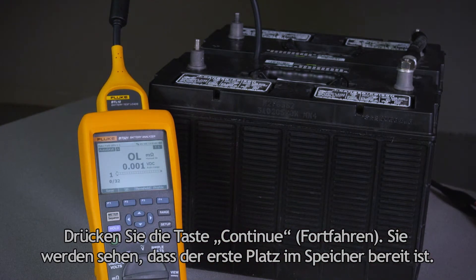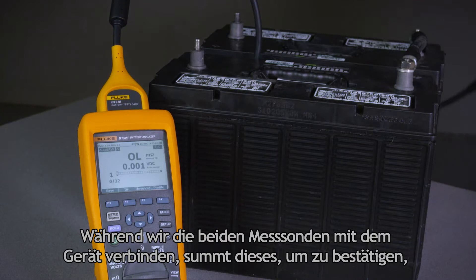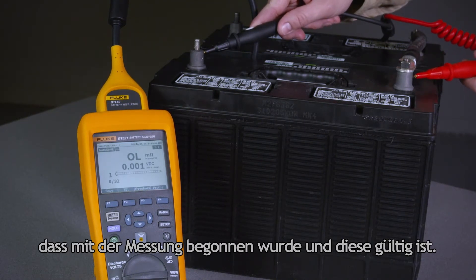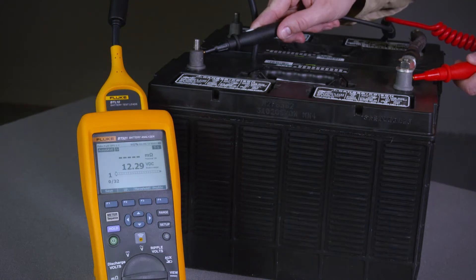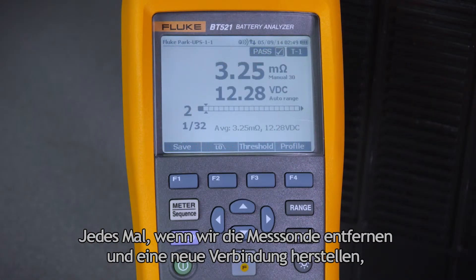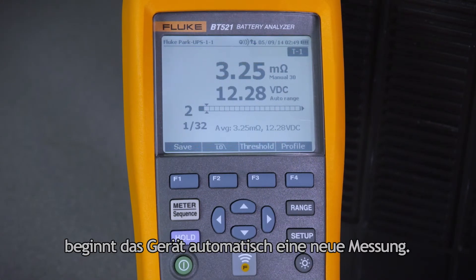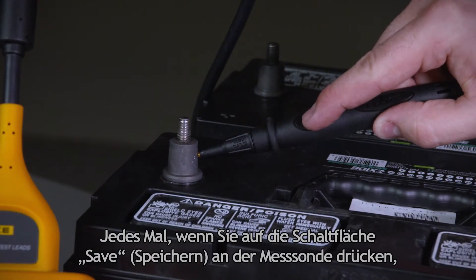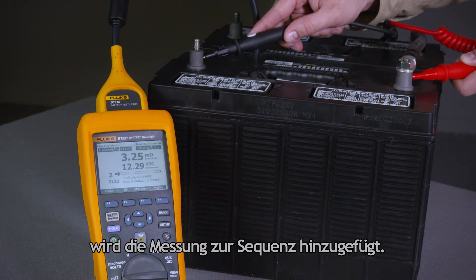You'll see that the first place in the memory is ready. As we connect the two probes, the instrument buzzes to confirm that it started the measurement and that the measurement is valid. Each time we remove the probe and make a new connection, the instrument automatically starts a new measurement. Each time you press the save button on the probe, that measurement gets added to the sequence.